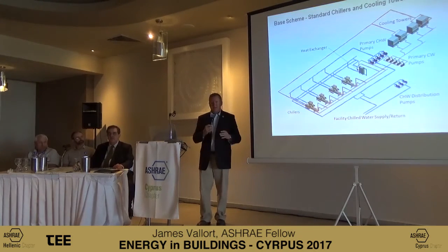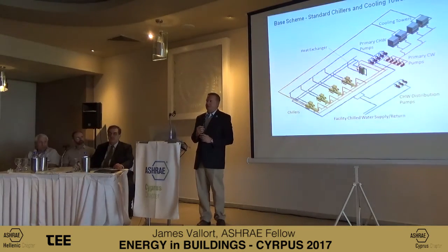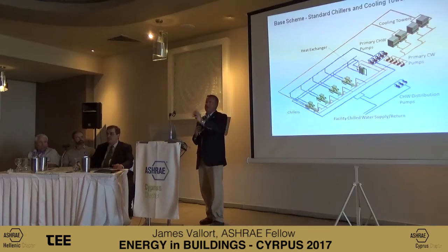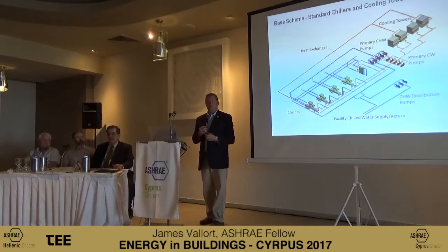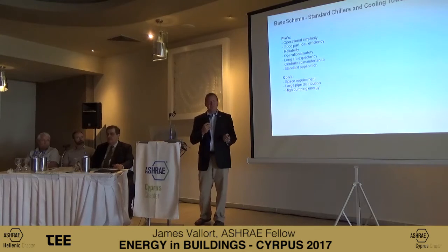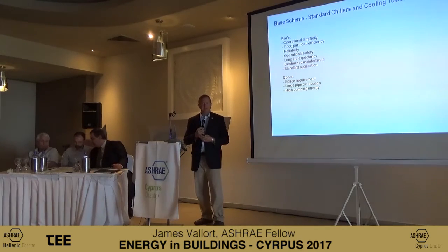Looking at the base scheme: this is nothing fancy — this is where you start when optimizing a chiller plant. You get creative after you pick your scheme, then dive into what control strategies and enhancements you use to tweak and gain energy efficiency. First, start with your basic unit: towers, primary and secondary pumping, and chillers. The pros are it's very simple, everyone's familiar with the configuration, it's reliable, and has a long life expectancy. The cons include piping costs and high pumping energy. Evaluate both pros and cons.